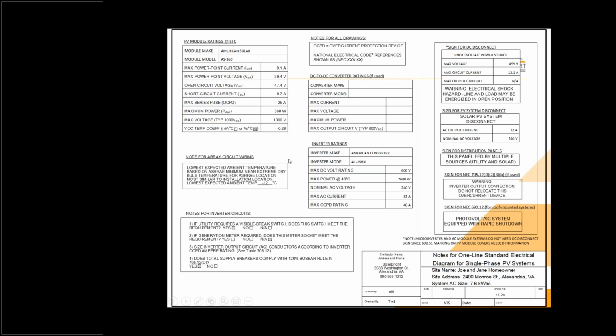Here are the specs on that module, and then the specs on the inverter, the sign for the DC disconnect, the sign for the interactive point of connection. The distribution panel needs this sign: panel fed by multiple sources, utility and solar. And then the circuit breaker where we interconnect to the panel needs a warning: inverter output connection, do not relocate this overcurrent device. And then since it's got rapid shutdown, it needs to have the sign: photovoltaic system equipped with rapid shutdown.